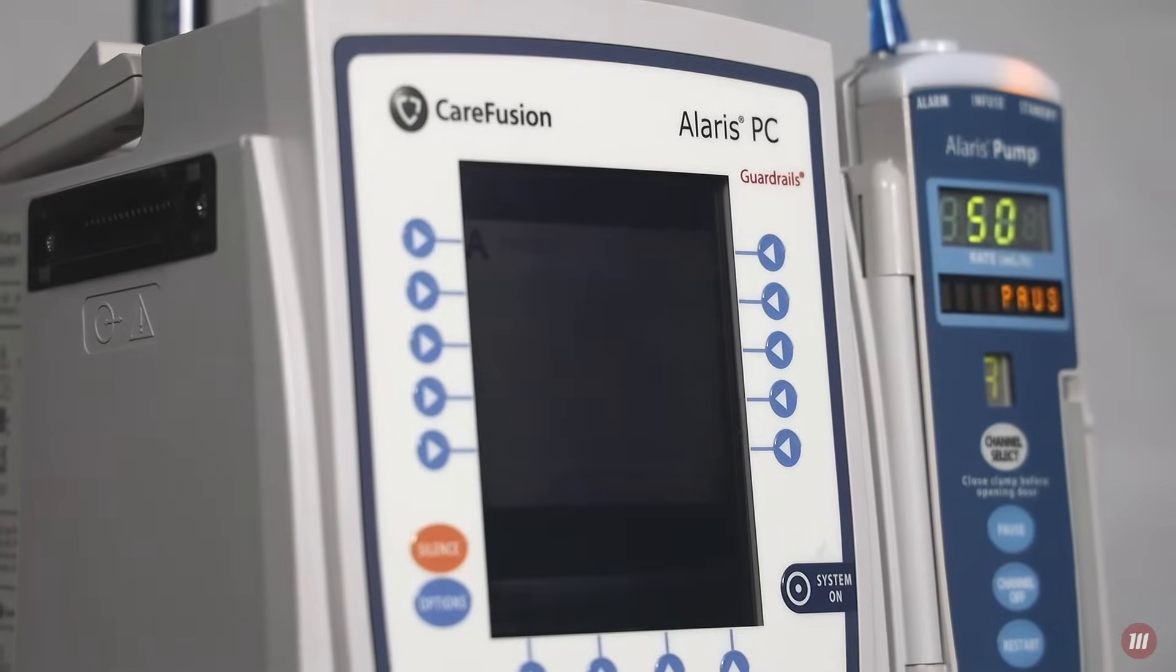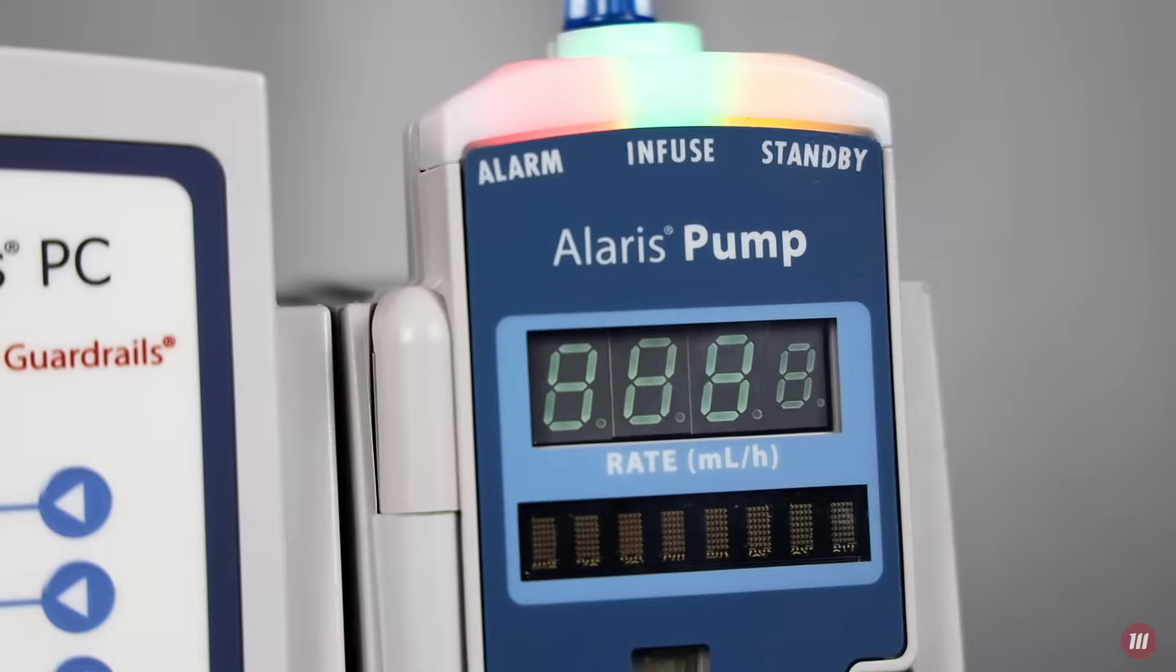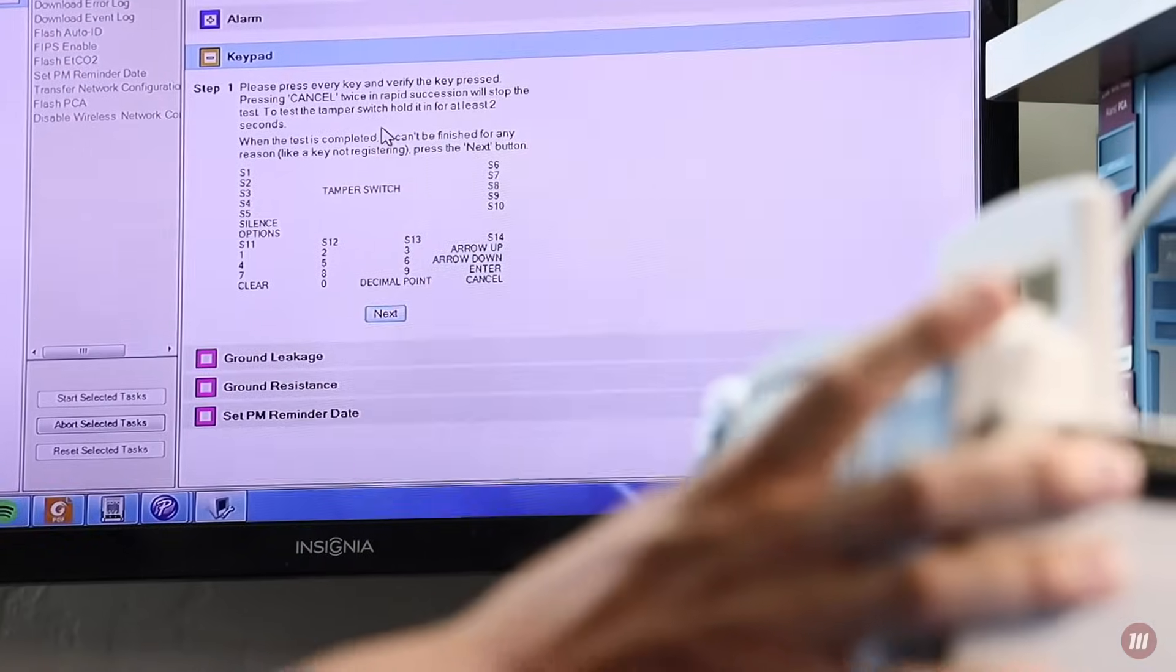Used for adult, pediatric, and neonatal patients, the Alaris system features Guardrails safety software to protect patients from infusion errors. Hospitals can create customizable drug libraries to fit the needs of each facility. The PCU can also be equipped with a demo drug library to be used for education purposes.